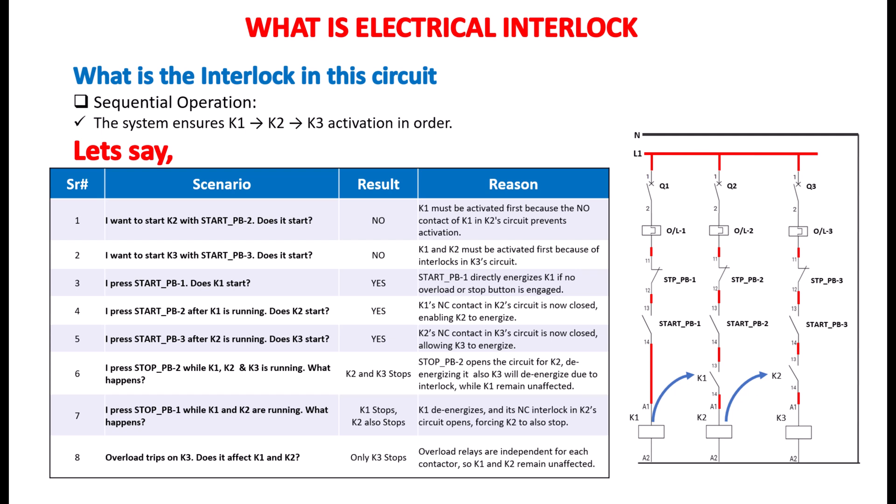Scenario 7. What if I press STOP PB1 while both K1 and K2 are running? In this case, K1 stops and K2 also stops. That's because stopping K1 opens its interlock in K2's circuit, cutting power to both.